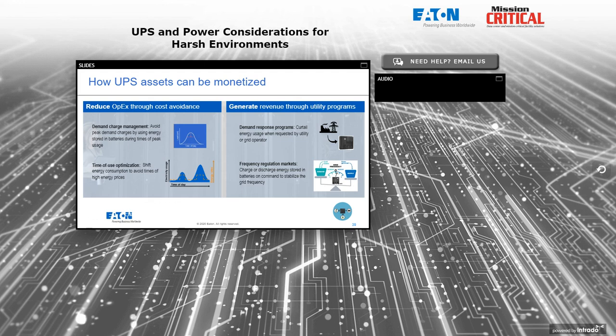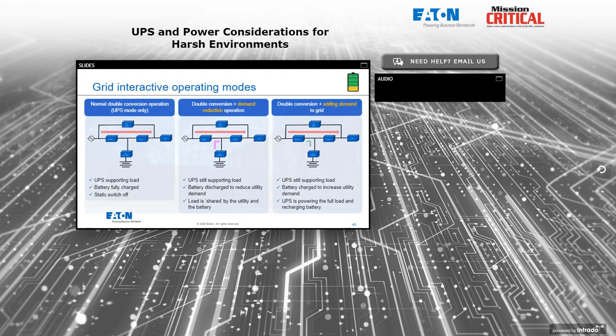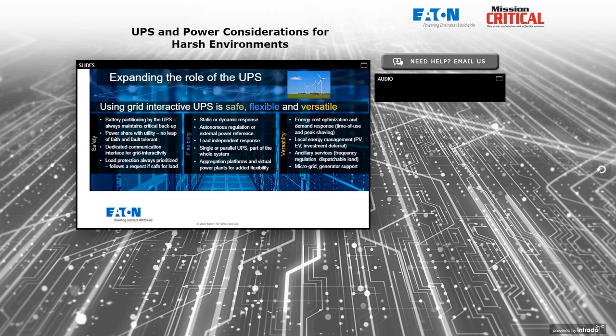Under high load conditions, the utility frequency drops a little bit. It's not allowed to drop much or else they have to take expensive action. Or they can basically regulate frequency in the positive direction. If necessary, if frequency drifts too high, the UPS can charge batteries during that time and actually reduce that. So those capabilities use traditional UPSs, traditional features with a few extra controls, and typically a lithium-ion battery that can tolerate the more frequent charge-discharge cycles that are necessary there.